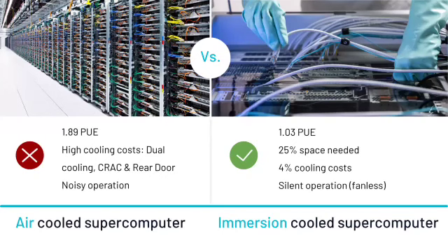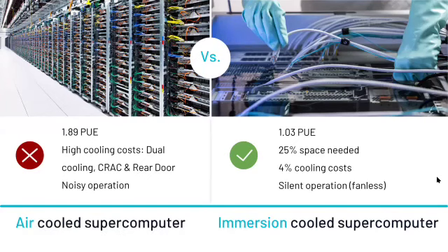Apart from that, talking about immersion cooling in general, not specifically about Submer today, it's possible to achieve PUEs of 1.03. We'll be talking about space saving and the economics, where you're spending only 4%, since 0.03 PUE, or 30 watts per kilowatt, is exactly 4% of that 1.89 PUE. We also have silent operation, so it's a totally different environment.